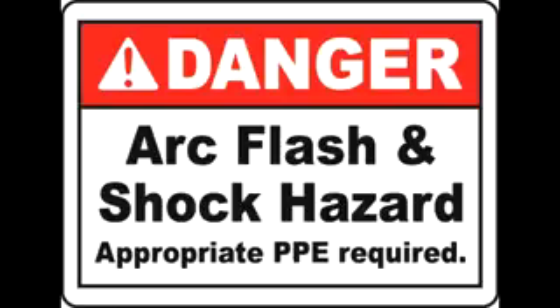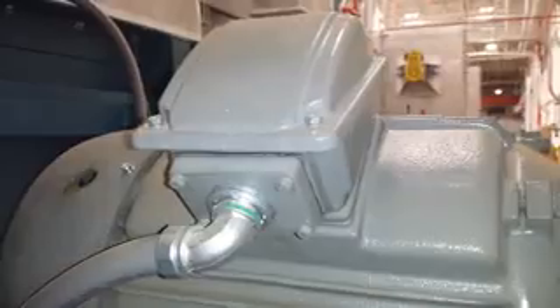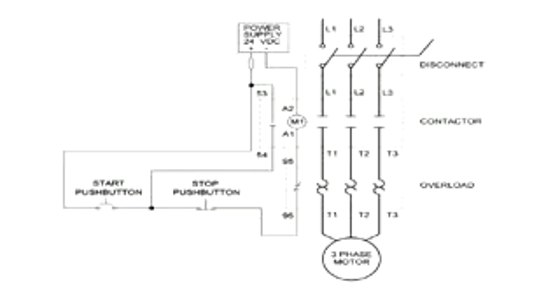What many YouTube videos will attempt to do is to teach the watcher to troubleshoot with the component already removed from the system. That's kind of impractical. Most of the time when you're doing this kind of troubleshooting, it's going to be in the system, not sitting idly by waiting for you to come along and test it. And what this doesn't teach the watcher is how this component interacts with the system. This is impractical, of course, to real-world troubleshooting. No motor is sitting idly by waiting to be checked. In the real world, the motor may take hours to tens of hours to remove from the system.